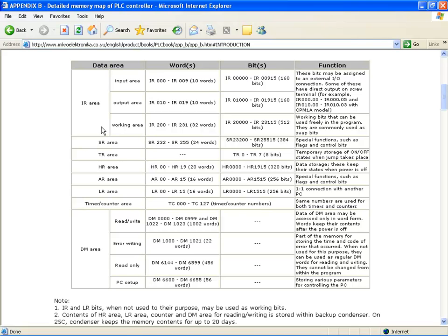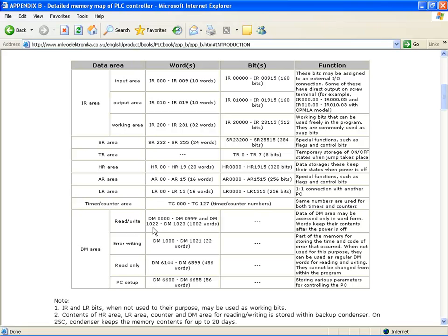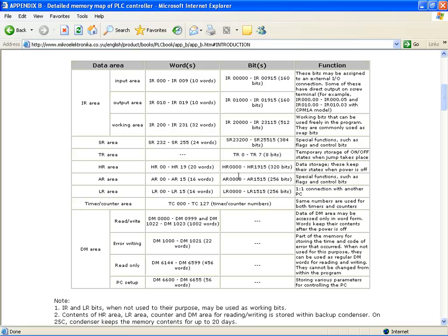I've got a generic memory map here rather than an SLC memory map because it's a little different. Here we have a table that shows us the data area, which is describing the particular data area or data use within the PLC, and there's some symbolic names which will be referred to further on in the documentation. You'll recognize timer counter areas, so there's an area set aside for timer counters and it's data memory area TC0 to TC127, telling us we've got 128 counters in this PLC. We've got a data memory area ranging from different types of data: read-only, read-write, error files. On the right hand side, the function of the particular data memory area is described. You used to have to know exactly where the memory was in each PLC. It's a little less complex these days. Let's have a look at the SLC memory map.